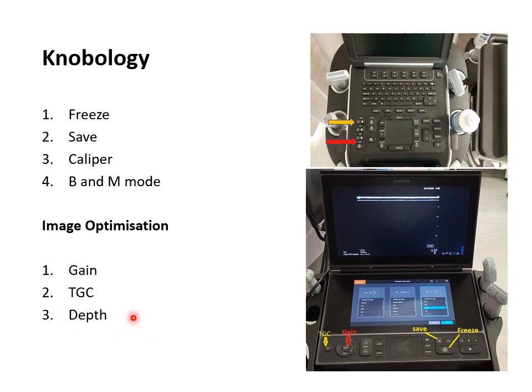Depth allows you to choose how far you want to send your sound waves. Try to use the least depth possible for the organ of interest. For example, if you are scanning a kidney located at 12 centimeters depth, try to use 12 to 14 centimeters — do not go to 20 centimeters, because the sound wave energy will be wasted. The depth scale appears on the side of the image.